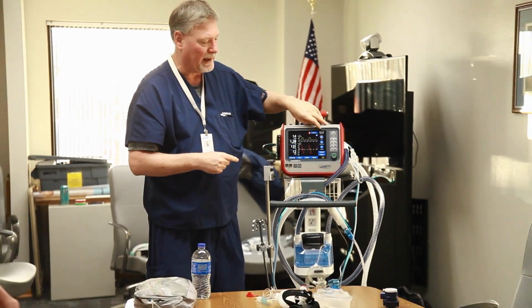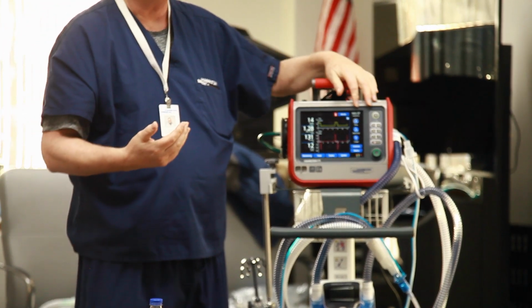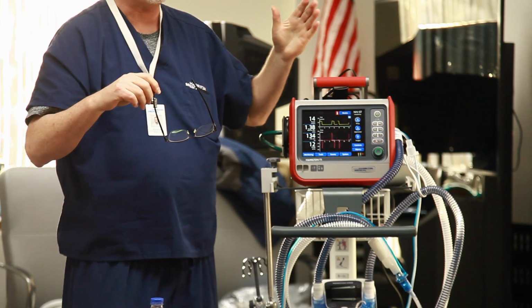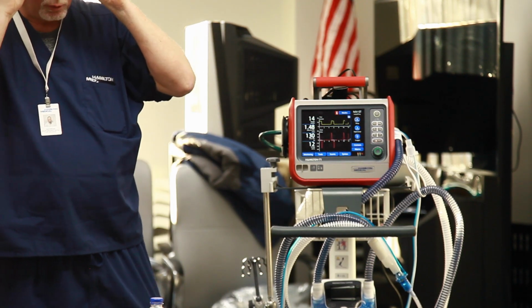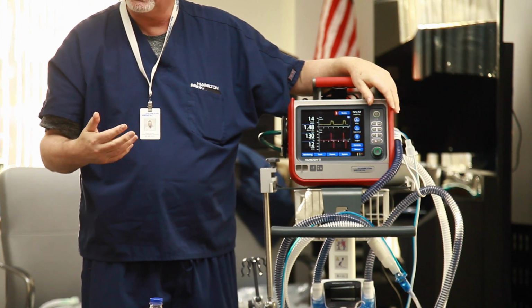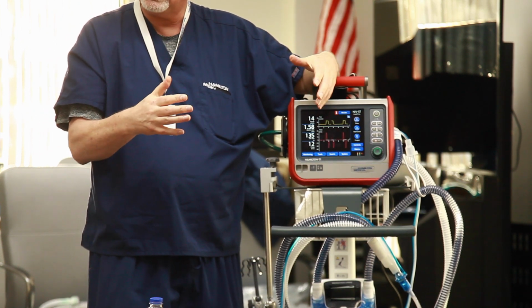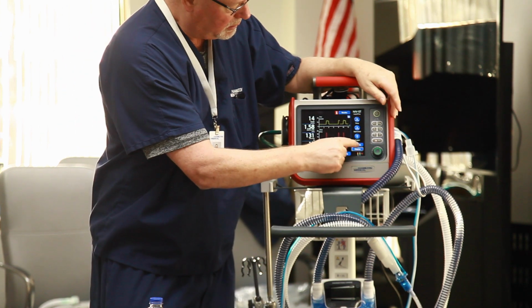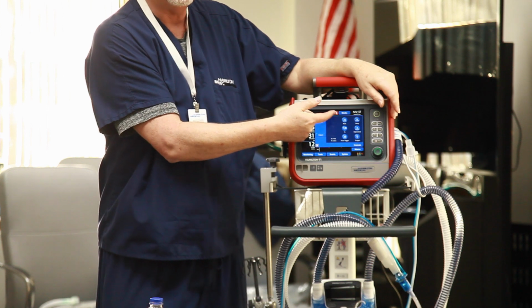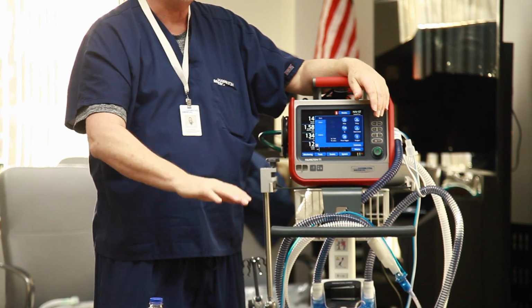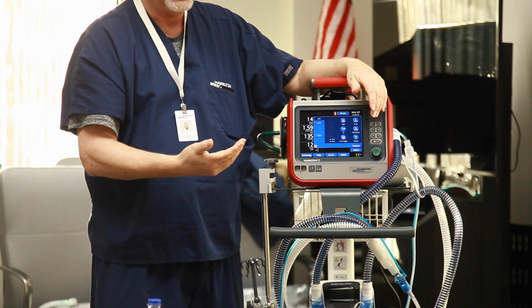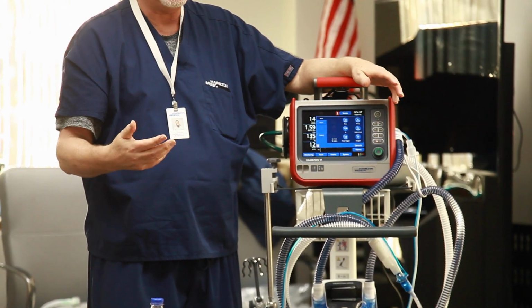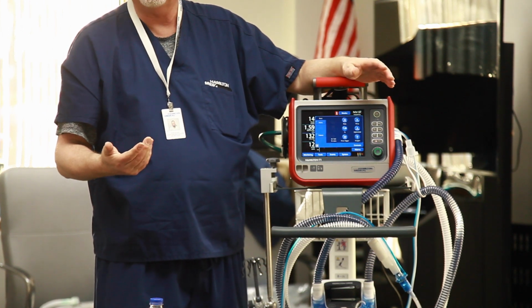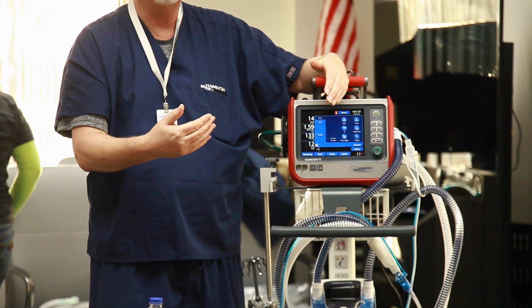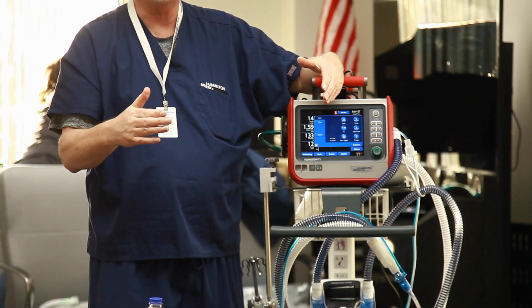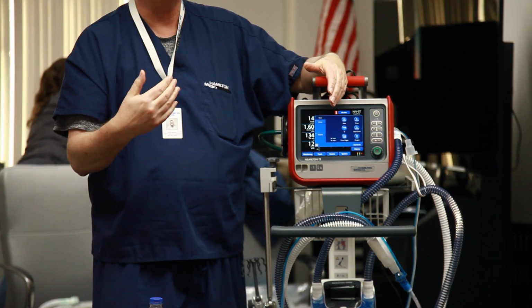So this is BiPAP. We call it non-invasive ventilation, ST. It's a little bit different. You probably just had BiPAP, there's no rate or anything. We pre-programmed the rate on here with the ST, spontaneous timed, just so there's a little bit of a backup rate behind it in case there's some apnea or something like that. So you're going to see that there's a rate that's set. It's all according to the height of the patient. So if you have somebody that's short, that rate might be at 15 or 16. Typically it's somewhere around 12 or so, give or take. Set that around 10 to 12. You don't want it too high that it's fighting with the patient a little bit, but you want it where if there is a period of time that there's not a breath, that it actually gives that patient a breath.